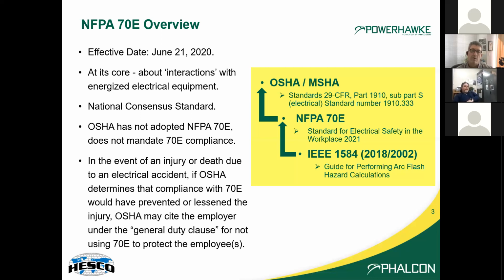Today we're really going to focus on the 2021 version in front of us now. So OSHA has the General Duty Clause, NFPA 70E talks specifically about electrical safety in the workplace, and IEEE supports both of that and supports 70E in that this is where the engineering calculations come in to guide the arc flash hazard analysis, the incident energy, and ultimately what gets you to PPE - personal protective equipment for your employees. This is how it all flows together.